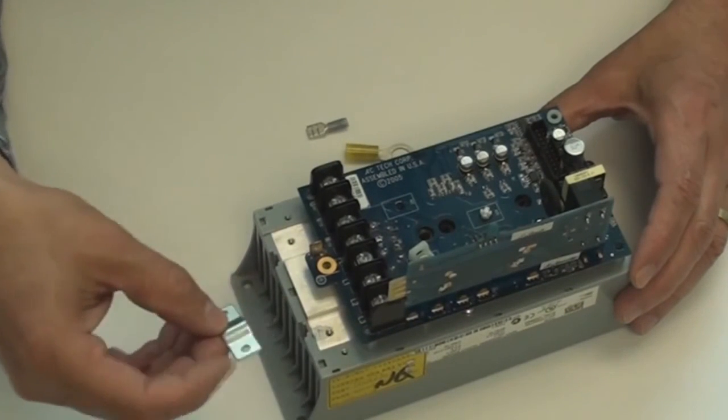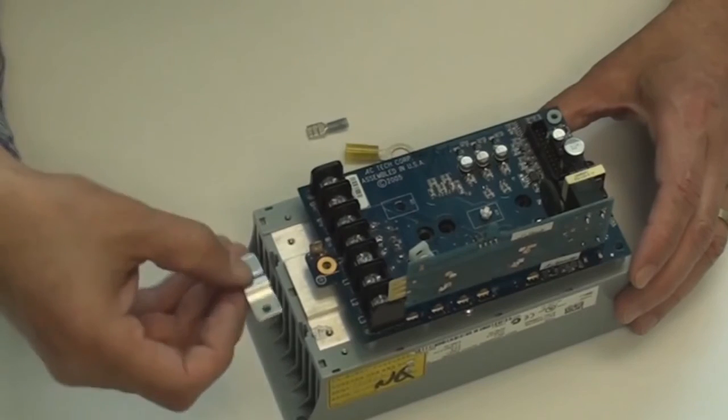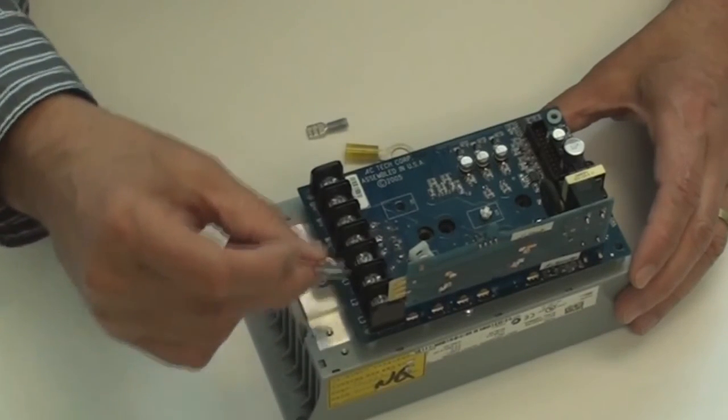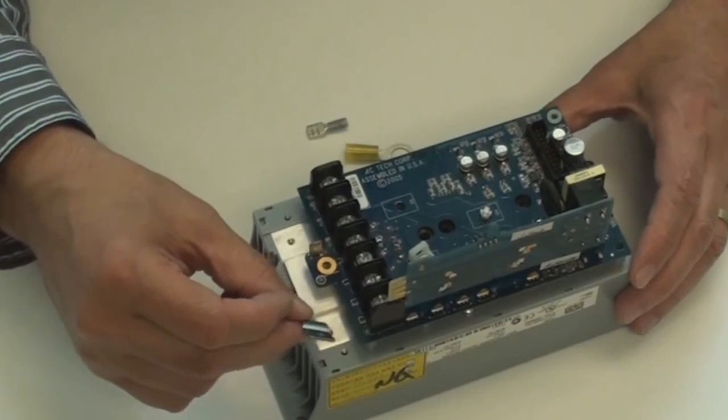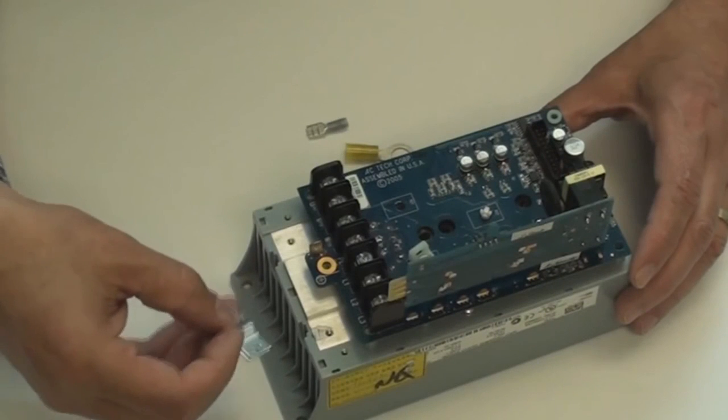Either way, as long as the cable for your control wiring is connected with the shield of this type plate, then the ground is going to be nice and firm and properly at the same potential as the drive, along with the cable going out to your motor.